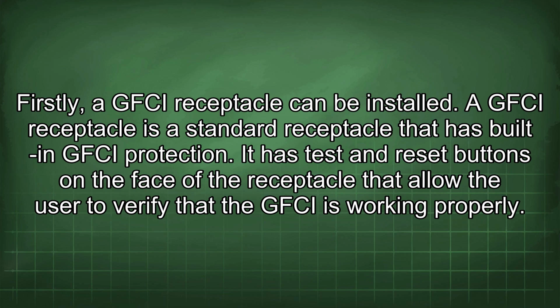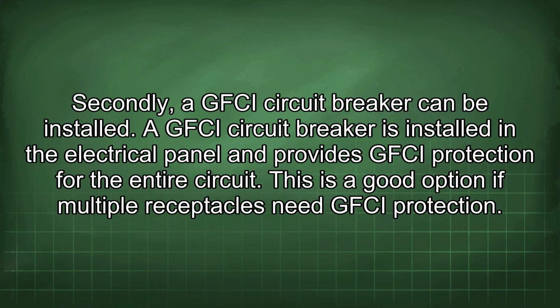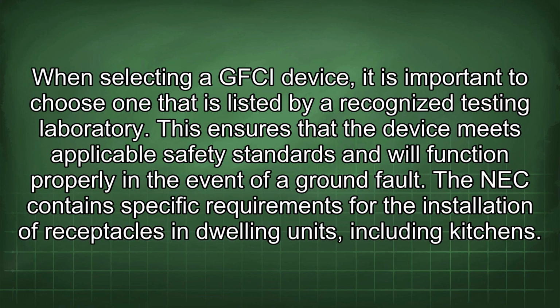A GFCI receptacle is a standard receptacle with built-in GFCI protection. It has test and reset buttons on the face of the receptacle that allow the user to verify that the GFCI is working properly. Secondly, a GFCI circuit breaker can be installed. A GFCI circuit breaker is installed in the electrical panel and provides GFCI protection for the entire circuit. This is a good option if multiple receptacles need GFCI protection. When selecting a GFCI device, it is important to choose one that is listed by a recognized testing laboratory. This ensures that the device meets applicable safety standards and will function properly in the event of a ground fault.